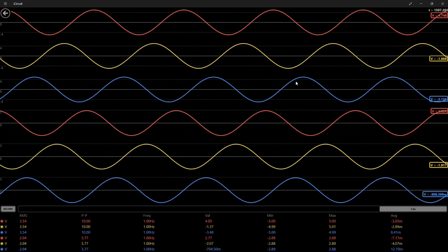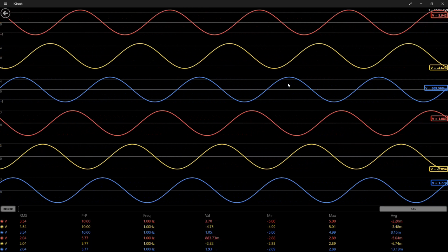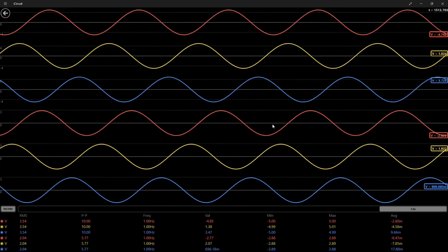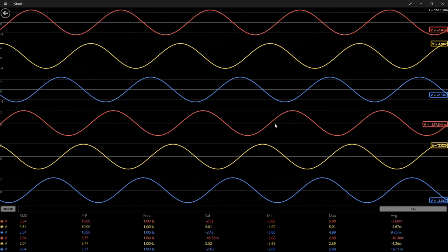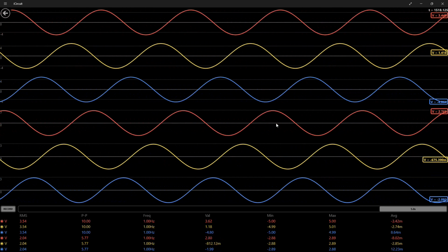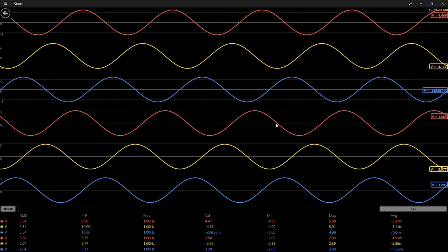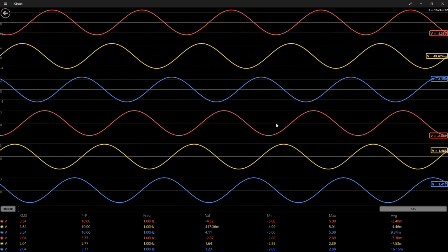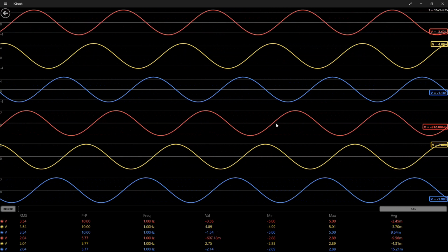But that's because it has a phase rotation that is reversed according to the nameplate. All nameplates are typically stamped as an ABC, not a CBA. And so that's what's going on. So hopefully this helps someone, and really cool. I'm absolutely okay with being right, or being wrong. If I'm absolutely wrong, I want to know why and learn from it. So hopefully someone else can learn from this too. So thank you.